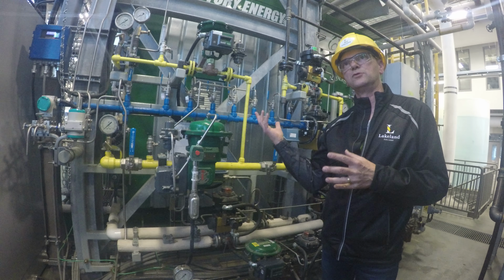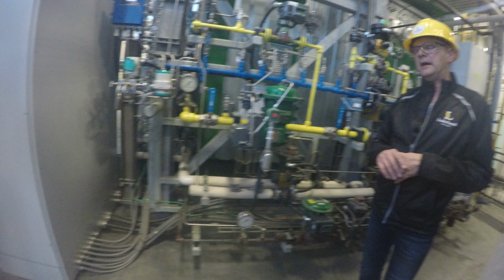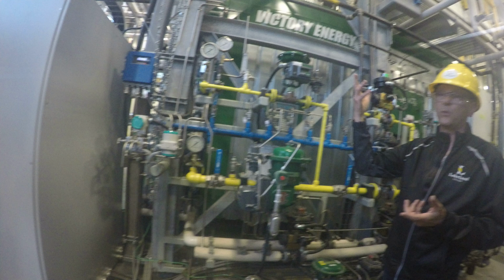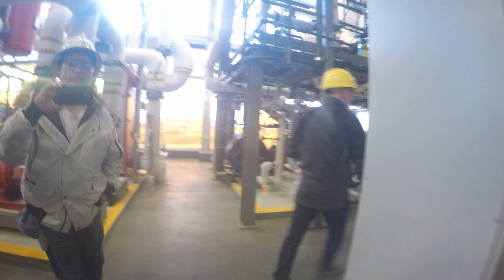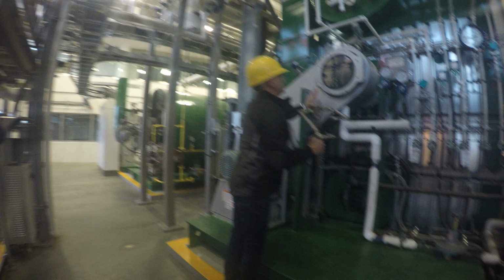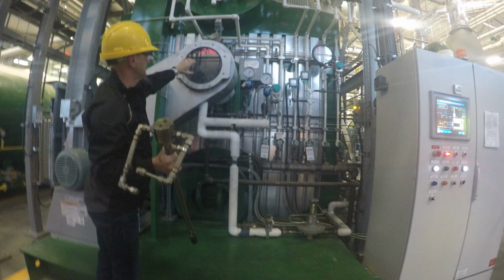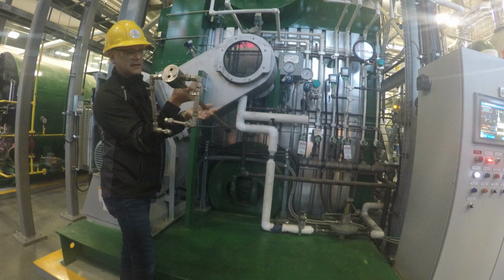It's a dual burn, so we can run natural gas and/or diesel. We just have to put in an oil gun. We have to open up the front door of the burner, and I'll show you here. Change the orifice or whatever. Actually, put an oil gun in here. What we'll do is take these off and open the door up, and just inside of the burner there's a cap. We move the cap out, and we slide that oil gun in.